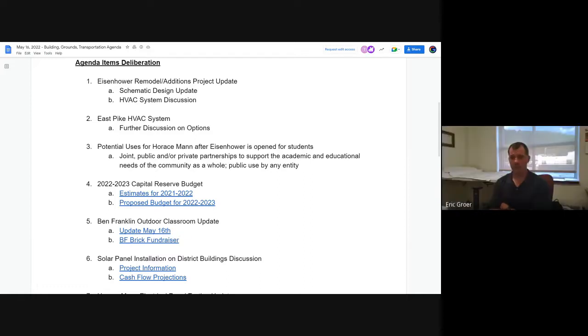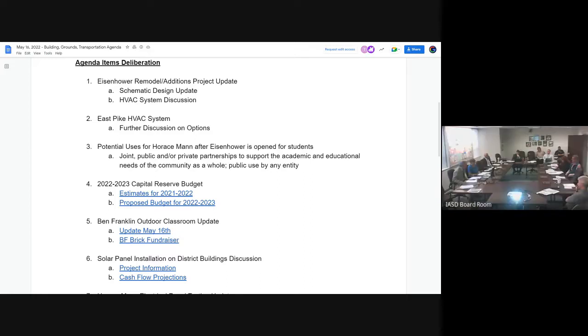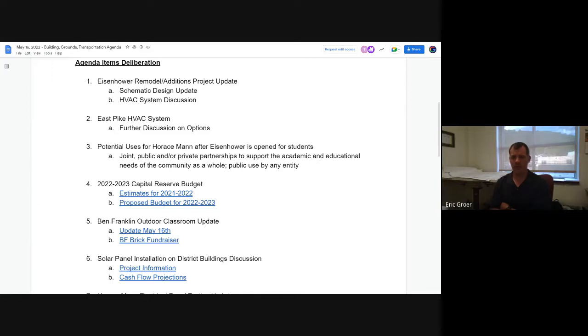Well, you haven't, if you have 120 tons of wells, and that's 500 square feet per well, per ton. This building is going to have a pretty diverse load. We're not going to have 400 people in the gymnasium and 200 people eating lunch and 200 people in the band room at the same time. We don't have that many kids. Well, that's true, we will take diversity into our calculations.